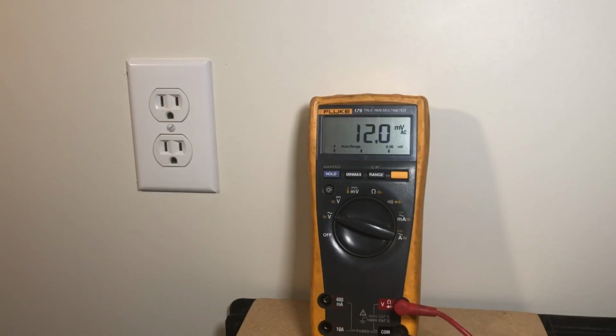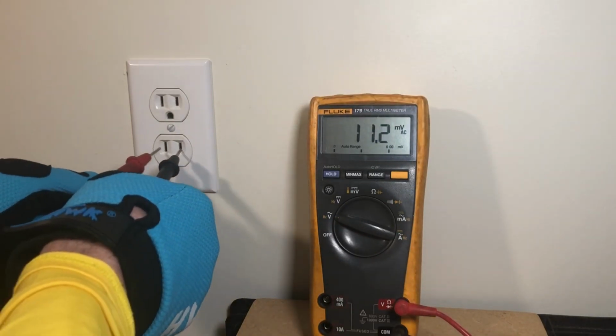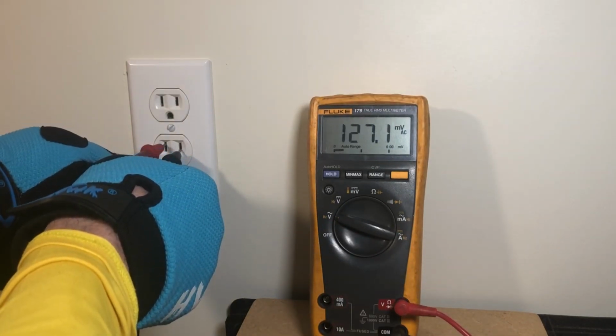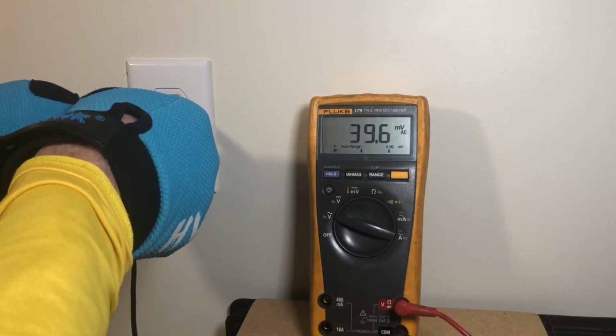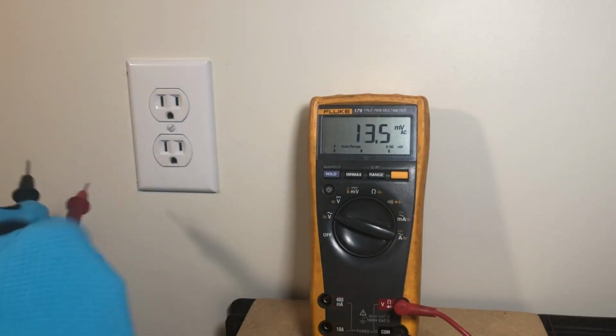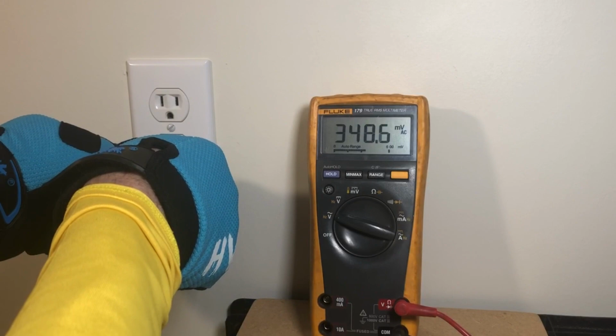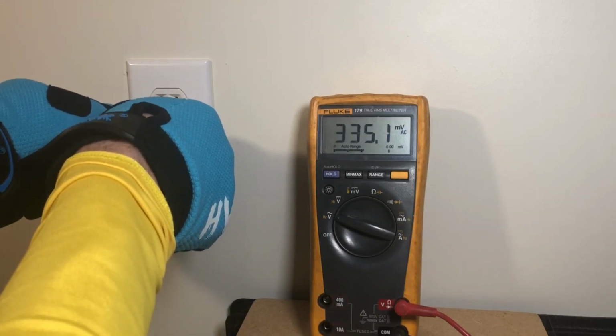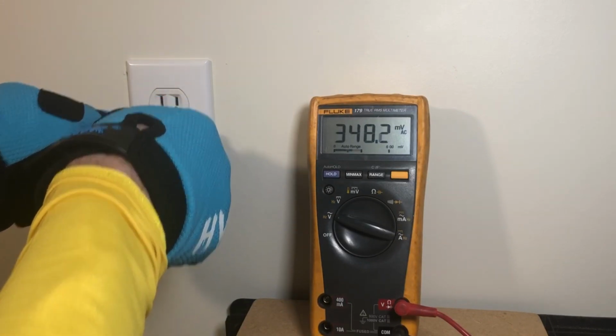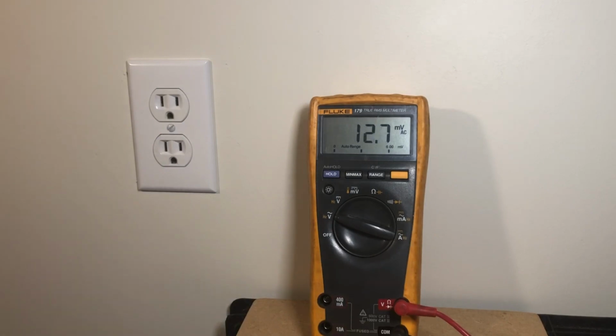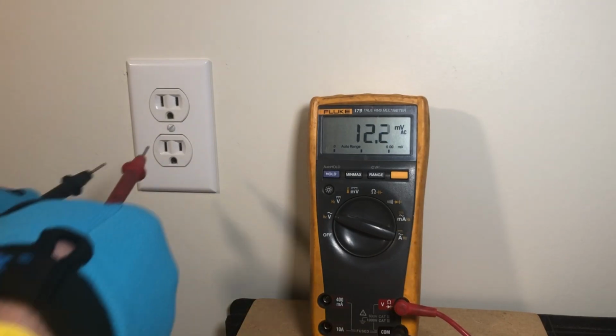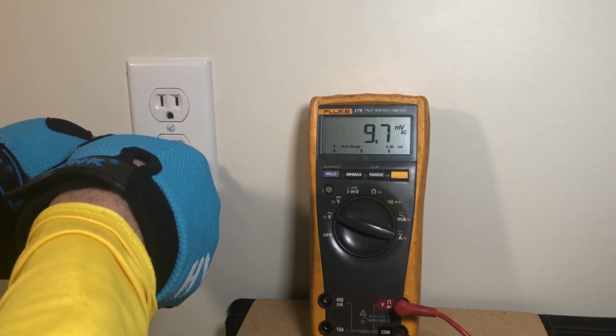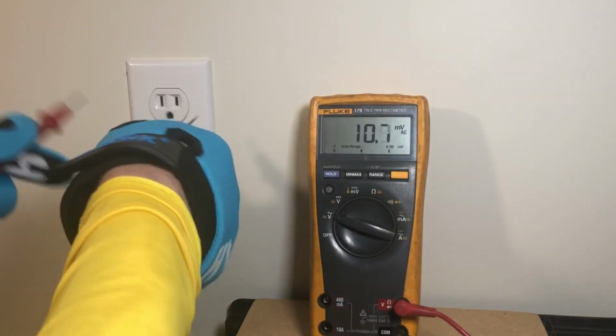A reading of 0 volts on the meter screen immediately points to a blown fuse, tripped circuit breaker, tripped ground fault circuit interrupter, or potentially faulty wiring. So, in this case, the next step is to troubleshoot this circuit and find the source of the problem. Oh, and you may not see exactly 0 volts on the meter, since there may be a bit of feedback voltage, but millivolt readings are close enough to 0 to indicate a lack of power at this outlet.